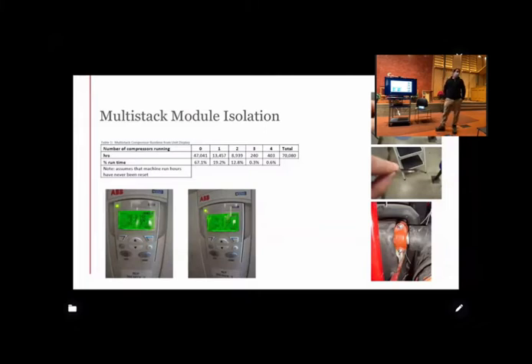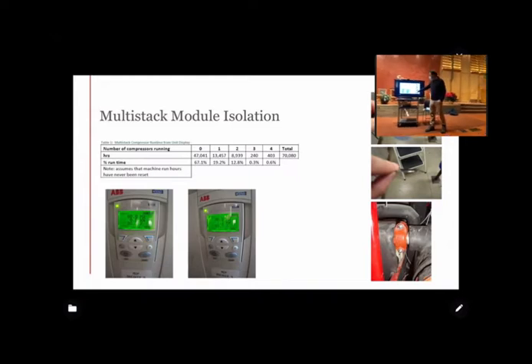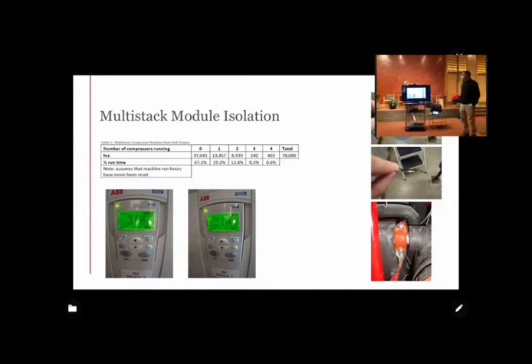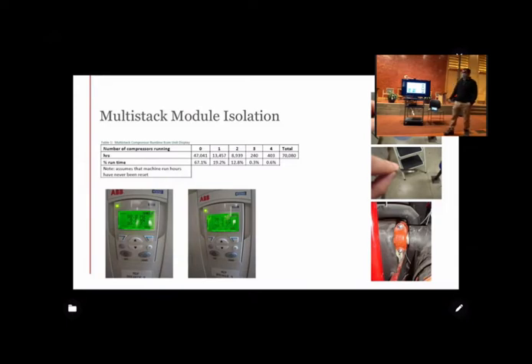Yeah, so I think a storage tank would have done a lot of good for the system, but I also think that a multi-stack, no one from Masters is here, the rep, but that unit has been kind of a lemon, to be honest. But anyway, we worked with Masters, and all it took is these little discs to isolate their, I'm blanking on the terminology, those Victaulic fittings. And we had a fitter come in, I think from General Heating, and we essentially just isolated one of the modules. So there's two units, each with two compressors, and we just basically valved off a unit.